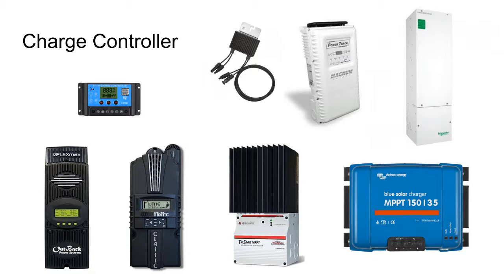I said, if you're a solar installer, you probably don't have a lot of experience installing charge controllers — that's not true actually, your SolarEdge DC Optimizer is a charge controller. I was just complaining about circuits that were only 150 volts, so you have 2 or 3 modules a circuit. Well, your SolarEdge DC Optimizer is 1 module a circuit, and it's a voltage regulator that regulates the voltage coming out of your solar array. That, in fact, is what a charge controller does — it regulates the voltage. So in National Electric Code, the term charge controller becomes the term voltage regulator.